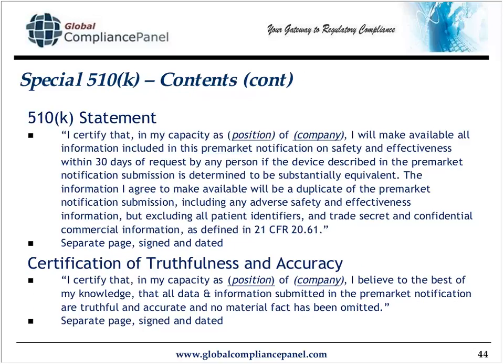And what I've done in this page is to give you the terminology that I've used in my 510K statement and in my certification of truthfulness and accuracy statement, both of which should be separate pages, should be signed, hand-signed, and dated on your letterhead.